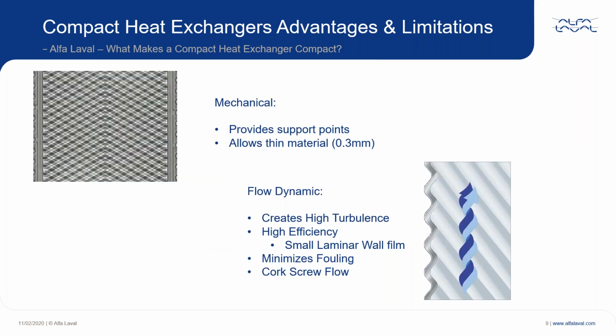And to make this happen, our plate heat exchangers have very thin plates. Some of our units now go down to 0.3 millimeters thick. The mechanical strength is actually provided by the chevron pattern and many contact points, making quite a rigid block. With the channel plates, you imagine these one put on top of the other and up the other way. The flow path is like a corkscrew effect, which creates a high turbulence, a small laminar wall film, and minimizes fouling.